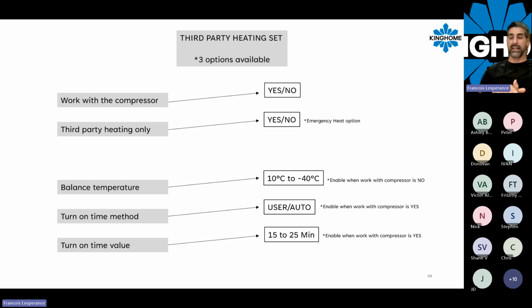So in a case that we have an emergency, for example, the heat pump has a leak and doesn't perform anymore in heating mode, and the customer wants to use only his baseboard at that point, well, we can turn on the third-party heating only, and the thermostat will act like a normal thermostat, +1, -1, activate the cooling, close, activate the heating baseboard, and shut it off.